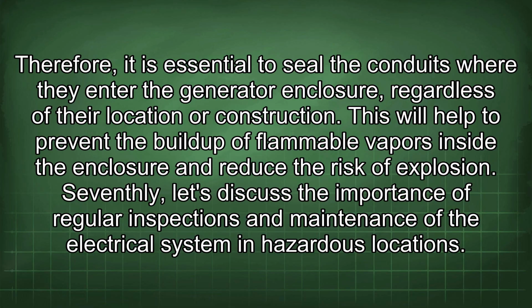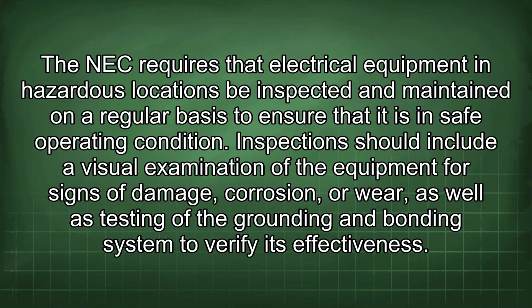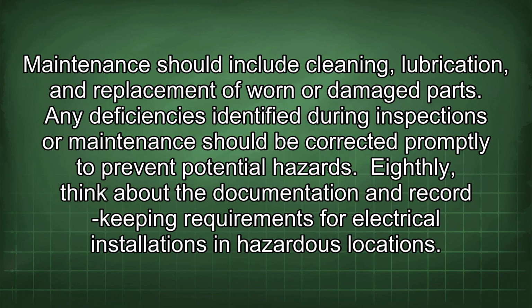Seventhly, let's discuss the importance of regular inspections and maintenance of the electrical system in hazardous locations. The NEC requires that electrical equipment in hazardous locations be inspected and maintained on a regular basis to ensure that it is in safe operating condition. Inspections should include a visual examination of the equipment for signs of damage, corrosion, or wear, as well as testing of the grounding and bonding system to verify its effectiveness. Maintenance should include cleaning, lubrication, and replacement of worn or damaged parts. Any deficiencies identified during inspections or maintenance should be corrected promptly to prevent potential hazards.